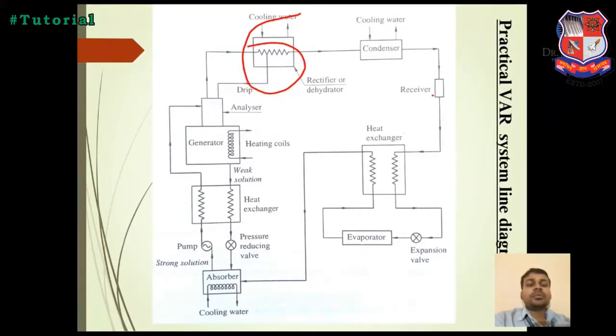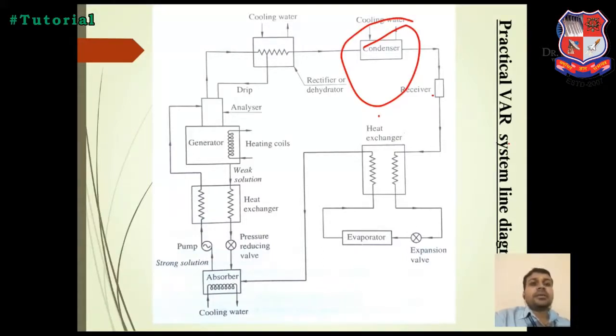the rectifier. Most of the H2O particles are separated in the analyzer. The remaining H2O particles are drained from the rectifier system. Some H2O particles pass through from the analyzer, and these H2O particles are separated in the rectifier, and pure NH3 vapor passes to the condenser. Pure NH3 vapor is passed through the condenser. The condenser rejects heat at constant pressure and constant temperature, at the latent heat of the NH3 vapor, and converts it into liquid NH3.